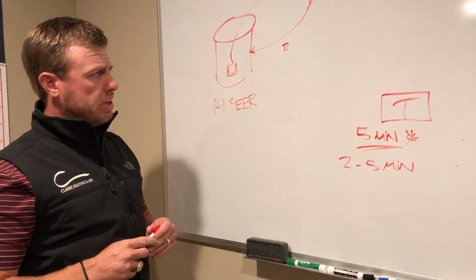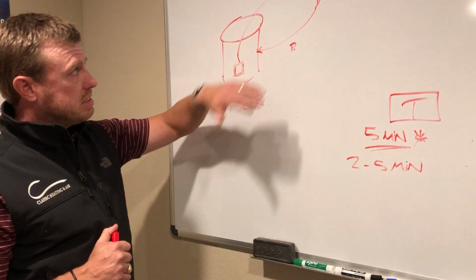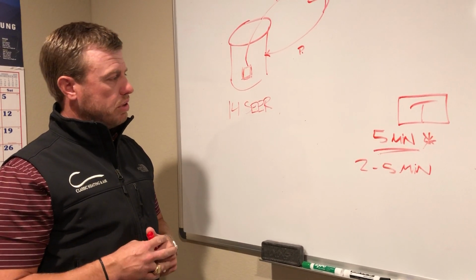A 5-minute delay will ensure that all systems of any type, brand, manufacturer can equalize, which will allow a certain and sure startup every time, no internal overloads, no problems.